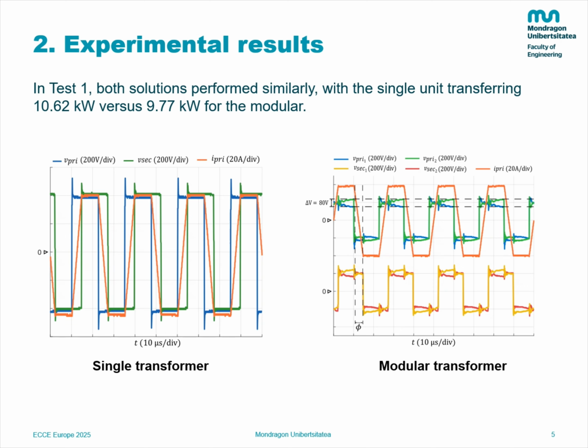When it comes to the AC voltages of the modular transformer, a non-equal voltage distribution is observed, especially during the period where the primary side current is flat. It must be then provoked by the magnetizing current of the transformer and the different magnetizing inductance values. However, the voltage difference measured at the end of the positive period is around 80 volts, which is 20% of the total 400 volts. On the other hand, the magnetizing inductance difference between each modular transformer is 217 microhenries, which is only 9.36% of the total magnetizing inductance.